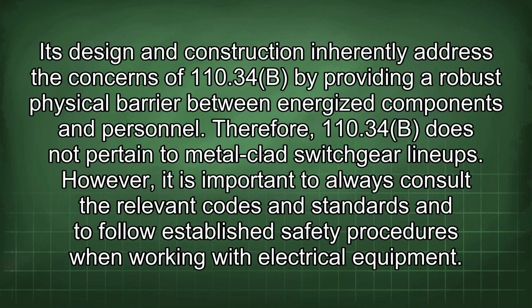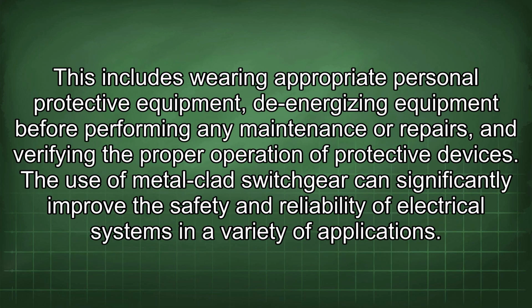Its design and construction inherently address the concerns of 110.34(B) by providing a robust physical barrier between energized components and personnel. Therefore, 110.34(B) does not pertain to metal-clad switchgear lineups. However, it is important to always consult the relevant codes and standards and to follow established safety procedures when working with electrical equipment. This includes wearing appropriate personal protective equipment, de-energizing equipment before performing any maintenance or repairs, and verifying the proper operation of protective devices.